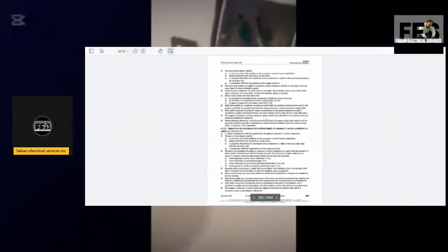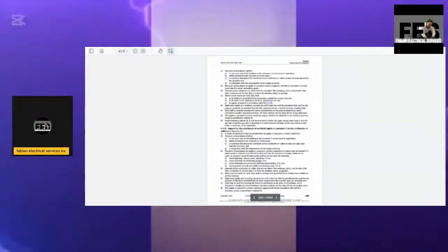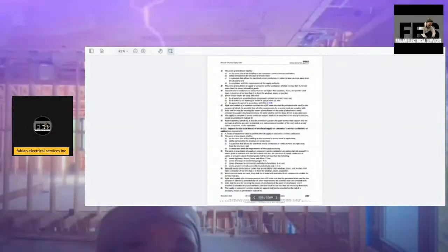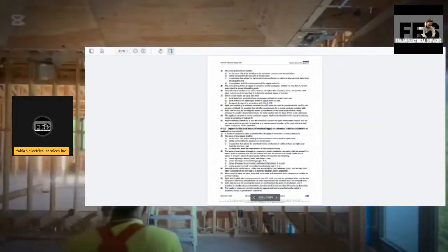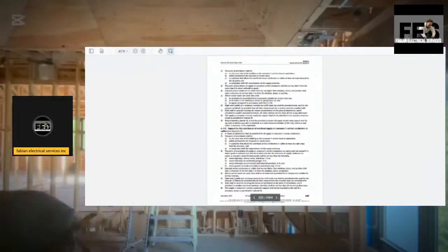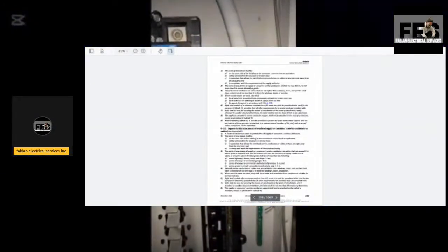The supply consumer service conductor support shall not be attached to the roof of a structure, except as permitted in Subrule 9. Notwithstanding Subrule 8, it shall be permitted to fasten the upper service mast support and the eye bolt to which a guy wire is attached to a main structure member of the roof, such as a roof rafter, a roof truss, or the equivalent.